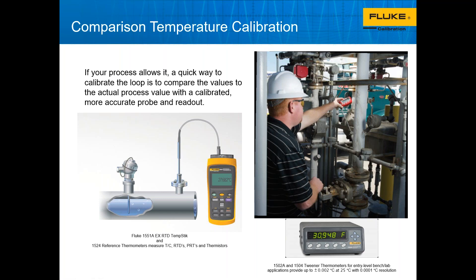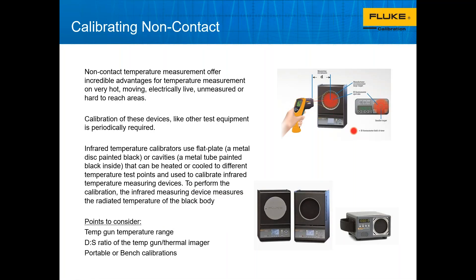There are also ways to calibrate non-contact temperature devices using what we call a black body source. These devices heat up to a surface that is considered a black body — 100% emissive — and you use a temperature gun or thermal imager to make a spot measurement on that surface. The controller tells you the actual temperature, and you compare that to your temperature gun reading. Different black body sizes are available — a small handheld portable one with roughly a 2.5 to 3-inch spot, and larger ones closer to 8 or 9 inches in diameter. Knowing your distance-to-spot ratio is important.